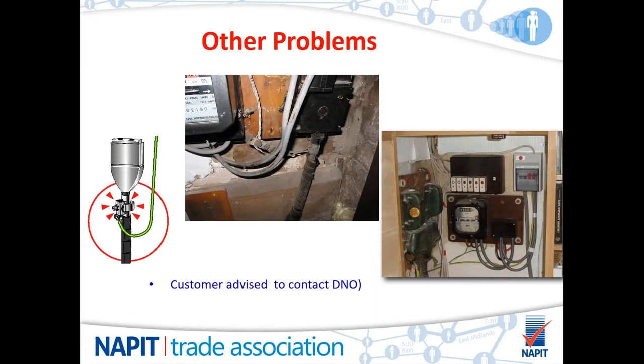Other potential problems you may come across when carrying out an EICR, such as a TNS system where a timber clamp has been used, the main earth, you may find that the connection is loose in itself. And as in the picture to the right hand side, you can see one of the older service cutout fuses where there is actually a protective fuse for both the line and the neutral, which again, like we spoke about before, wouldn't be ideal. In these instances, you would be advised to contact the DNO.